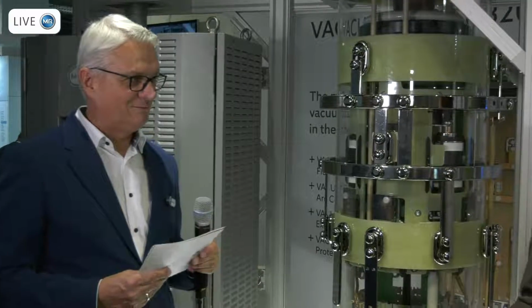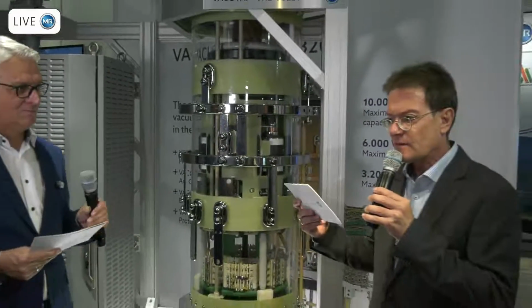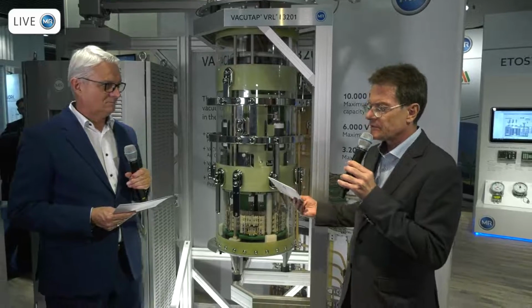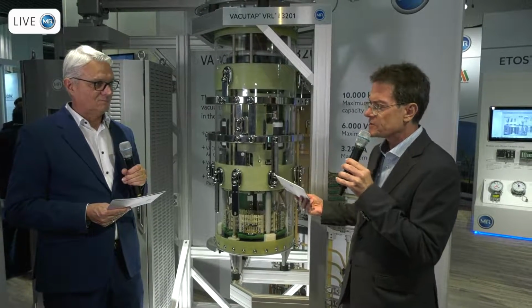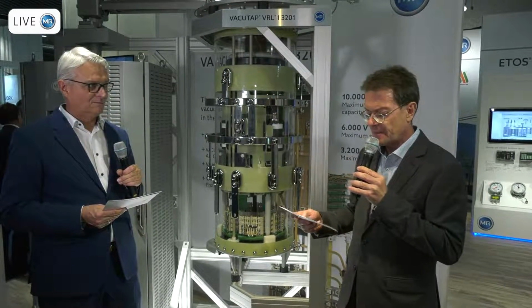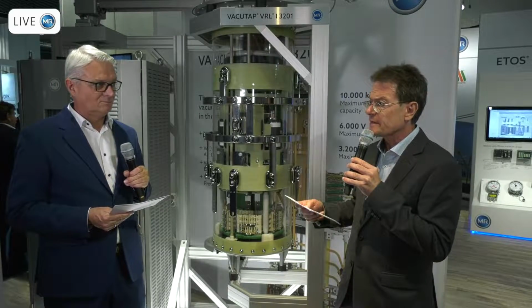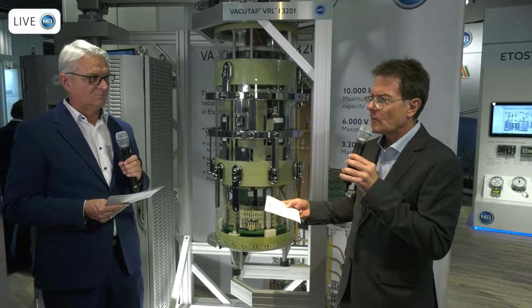One of the keywords you mentioned is we don't need the current splitting anymore. I think this does make the OEM happy. Are there other advantages for the OEM that you can mention? Yes, of course. Basically, one tap changer of VRL 3200 replaces 2 tap changers in parallel by this capability. This offers the possibility either to reduce the size of the tank or to put an even higher power rating in the existing tanks. This is a feature very welcome by the OEMs.